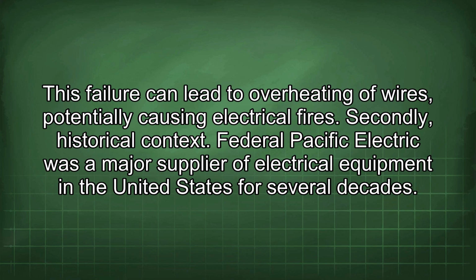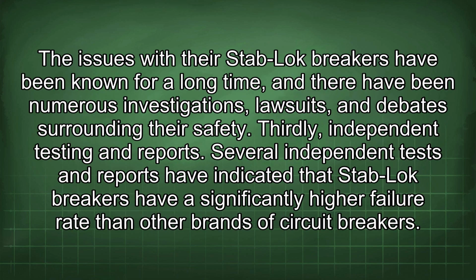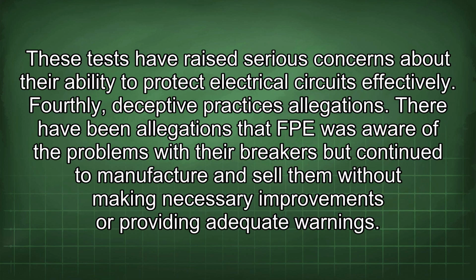Secondly, historical context. Federal Pacific Electric was a major supplier of electrical equipment in the United States for several decades. The issues with their Stab-Lok breakers have been known for a long time, and there have been numerous investigations, lawsuits, and debates surrounding their safety. Thirdly, independent testing and reports. Several independent tests and reports have indicated that Stab-Lok breakers have a significantly higher failure rate than other brands of circuit breakers. These tests have raised serious concerns about their ability to protect electrical circuits effectively.